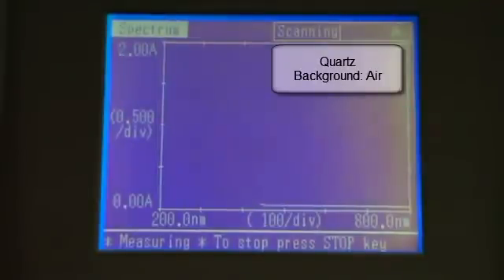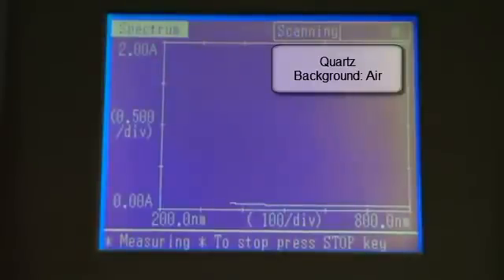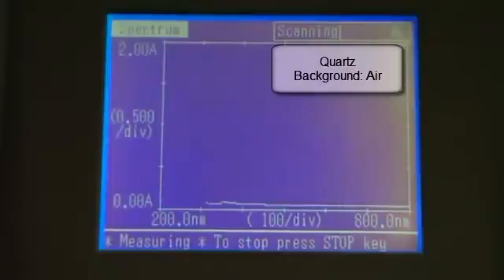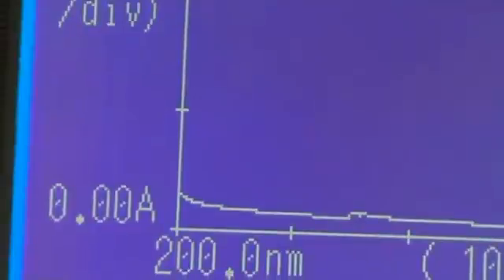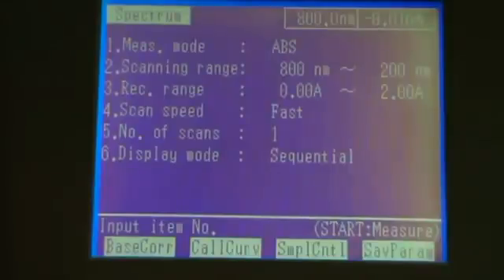Finally, it's quartz. We see that quartz is the ideal cell. It has a window right across the UV visible range, and does not absorb anywhere in this region. It's expensive, and that's why we don't use it as often as we might. Quartz's cut off is actually around 190 nm.